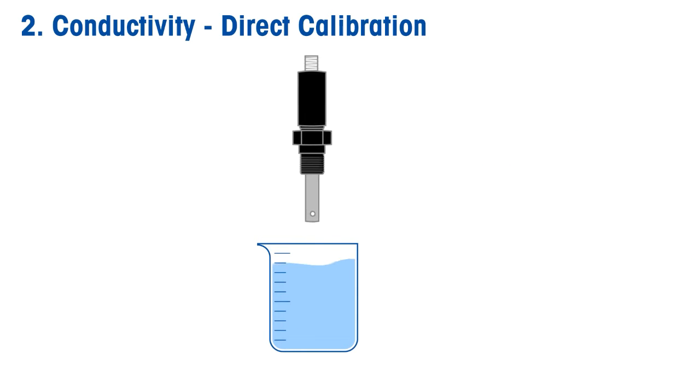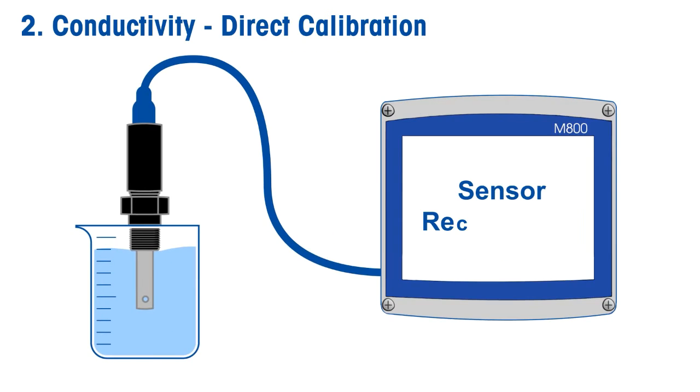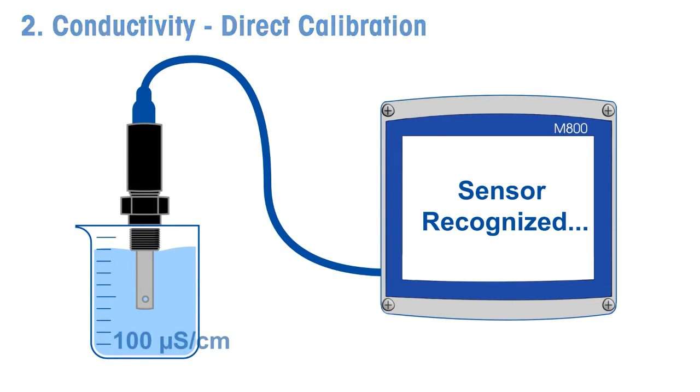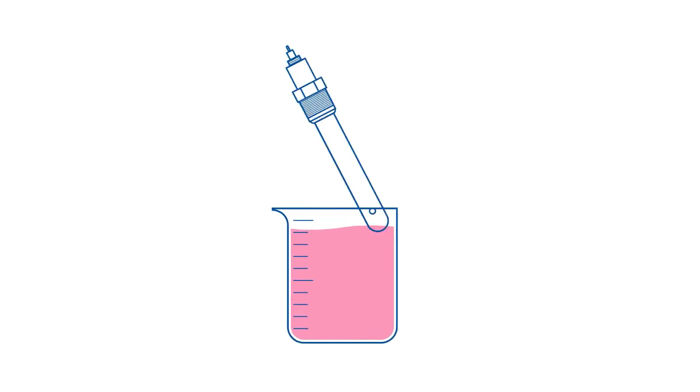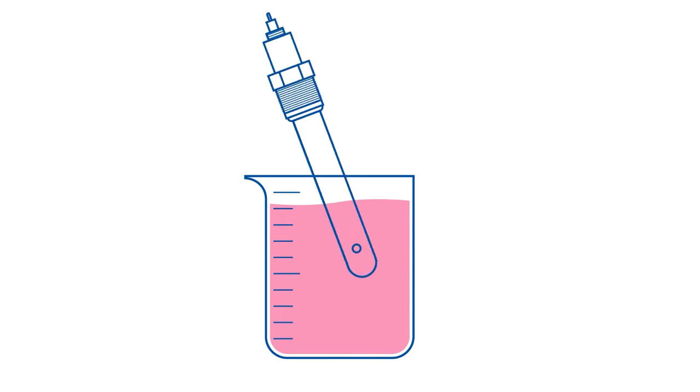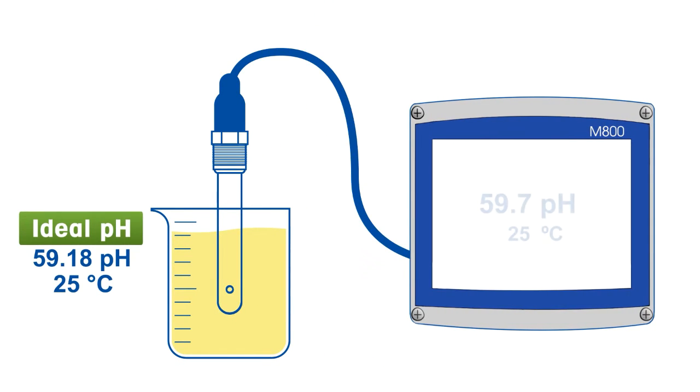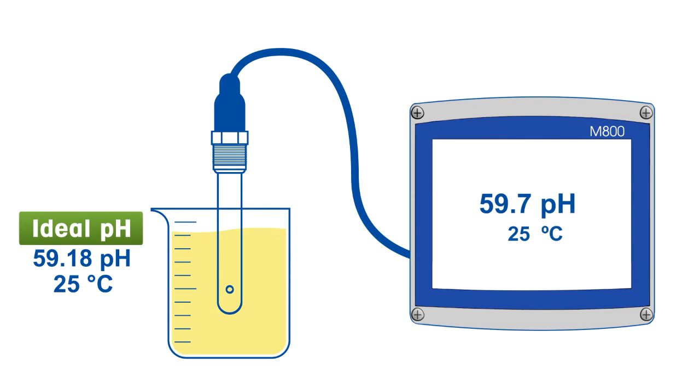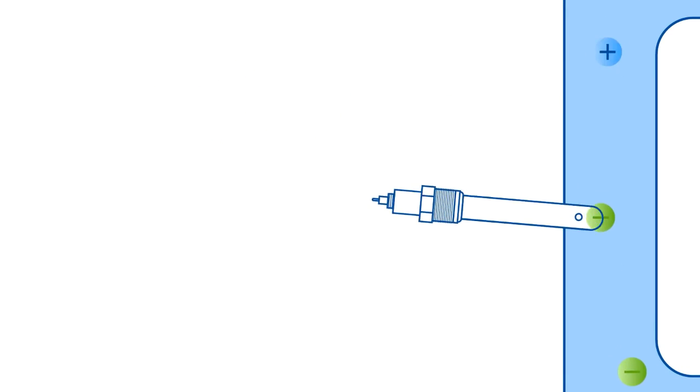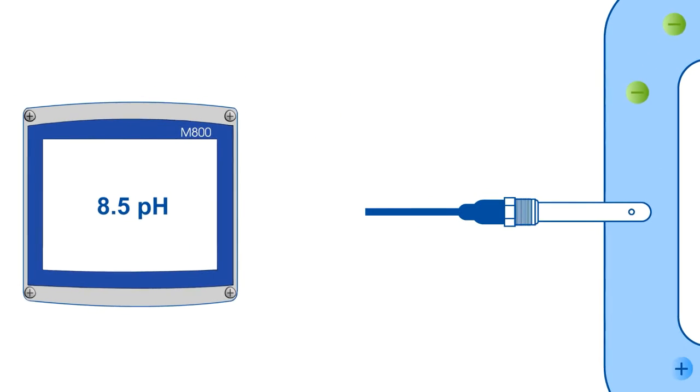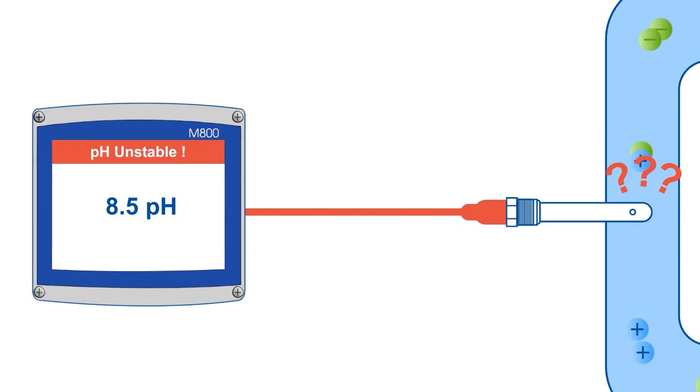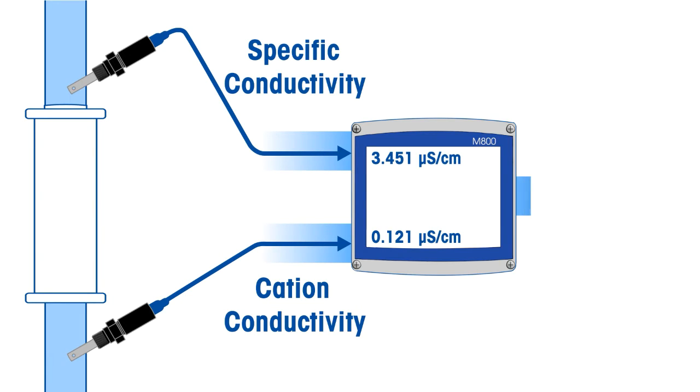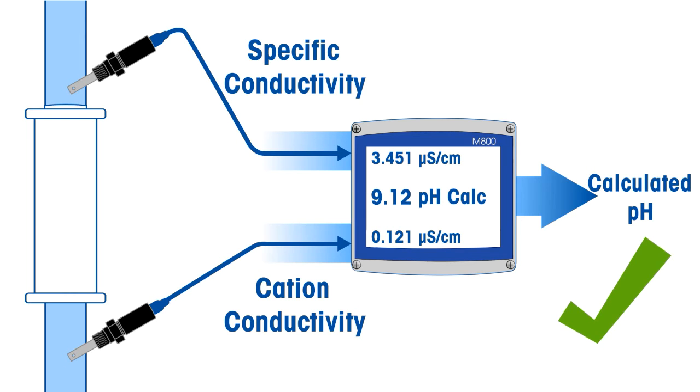Second, conductivity sensors can be directly calibrated with minimal introduction of error. All pH reference electrodes have a variable junction or diaphragm potential that can change between buffer calibration and process measurement, introducing some uncertainty to subsequent measurements.